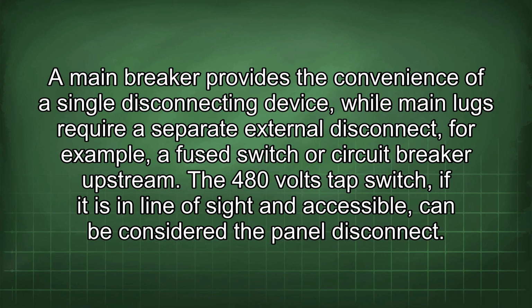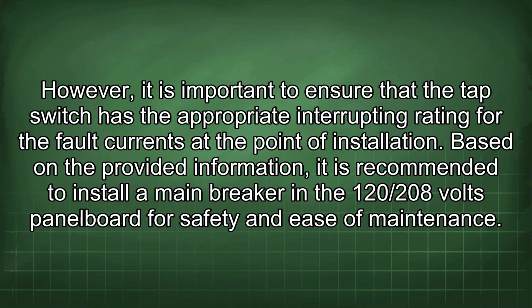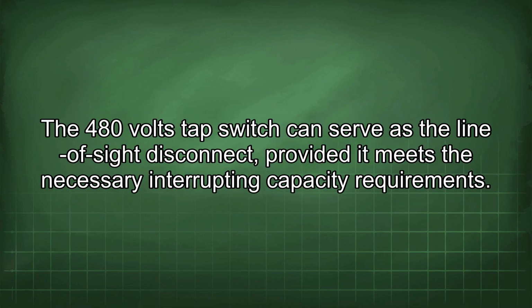The 480 volts tap switch, if it is in line of sight and accessible, can be considered the panel disconnect. However, it is important to ensure that the tap switch has the appropriate interrupting rating for the fault currents at the point of installation. Based on the provided information, it is recommended to install a main breaker in the 120/208 volts panel board for safety and ease of maintenance. The 480 volts tap switch can serve as the line of sight disconnect, provided it meets the necessary interrupting capacity requirements.